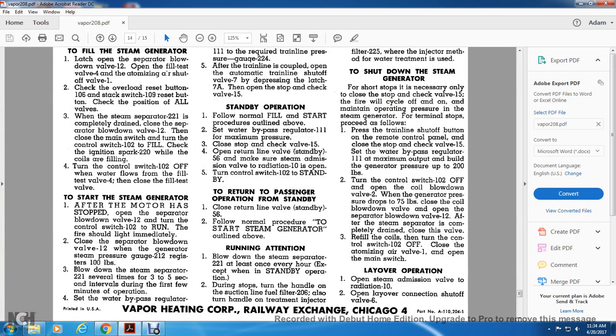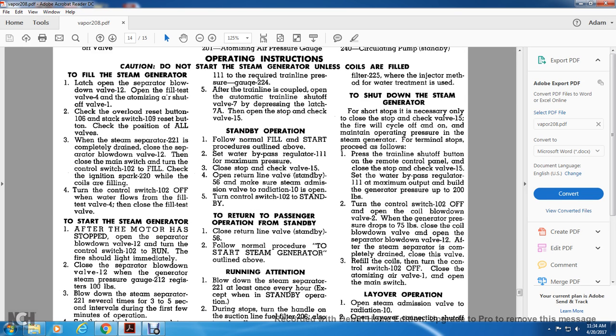Running attention: blow down the steam separator 221 at least once every hour, except during standby operation. Turn the handles on the suction line fuel filter 206 and the treatment injector filter 225 if the injector method of water treatment is used. To shut down the steam generator for short stops, it is necessary only to close the stop and check valve 15. The fire will cycle off and the steam generator will maintain operating pressure. For terminal stops, proceed as follows. Press the train line shutoff valve button on the remote control panel and close the stop and check valve 15.